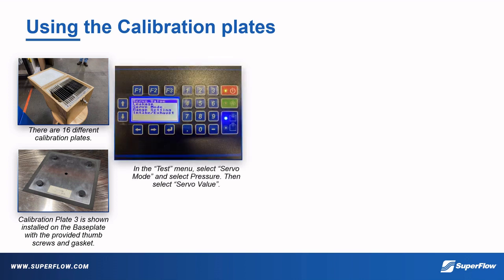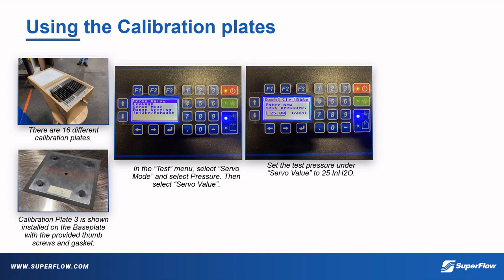From the main menu, press F3 to enter into the test menu and select Servo Mode. Make sure pressure is selected. Then, back in the test menu, select Servo Value. When in this menu, set the test pressure to 25 inches H2O and press Enter.